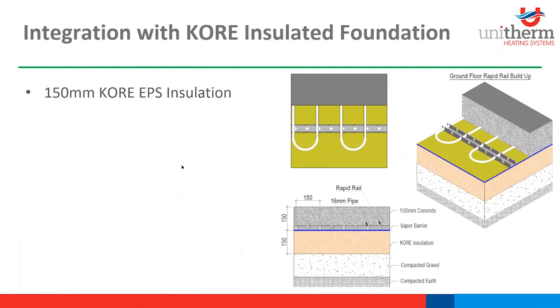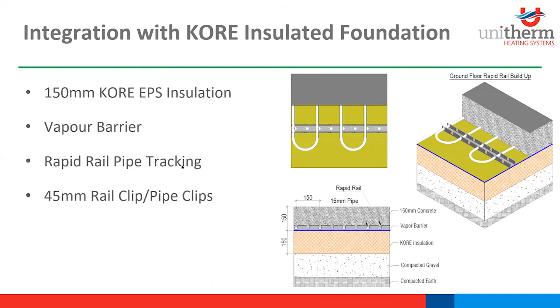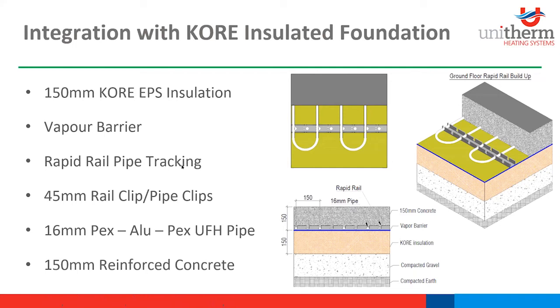Just the floor build up here for KORE's insulated concrete foundation. We start with our earth, so our compacted gravel on our site. Then we go with 150 mil KORE EPS insulation. That's 150 mil on average, as Andrew talked about recently. It goes from 100 to 300, but 150 on average. Then you have your vapor barrier required, rapid rail pipe tracking, 45 mil clips to clip the tracking into the insulation, 16 mil PEX underfloor heating pipe, which is PEX with an aluminium oxygen barrier and PEX again on the outside, and then 150 mil reinforced concrete.